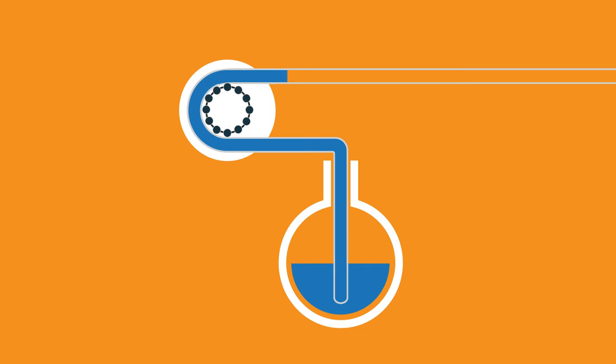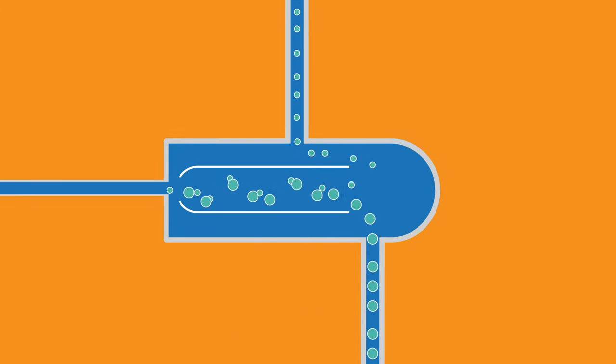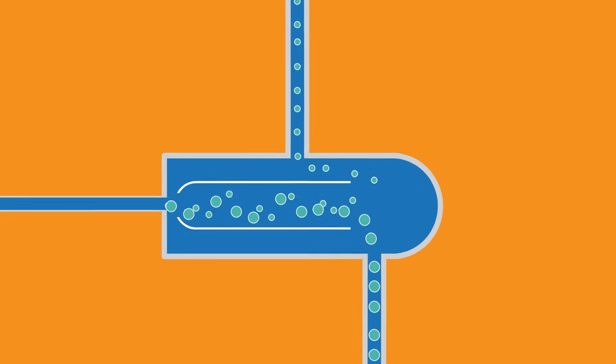The liquid sample is drawn into the peristaltic pump. In the nebulizer, it's converted into a fine aerosol spray. In the spray chamber, larger droplets drain away, but finer droplets are directed into the hot plasma.